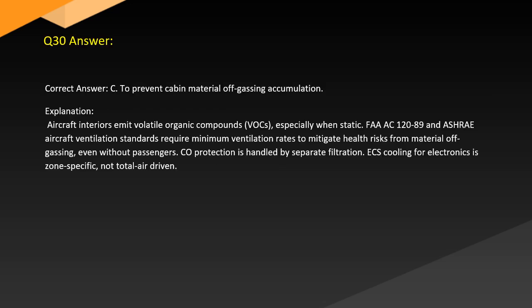Answer. Correct answer: C. To prevent cabin material off-gassing accumulation. Explanation: Aircraft interiors emit volatile organic compounds, VOCs, especially when static. FAA AC 120-89 and ASHRAE aircraft ventilation standards require minimum ventilation rates to mitigate health risks from material off-gassing even without passengers. CO protection is handled by separate filtration. ECS cooling for electronics is zone-specific, not total air-driven.